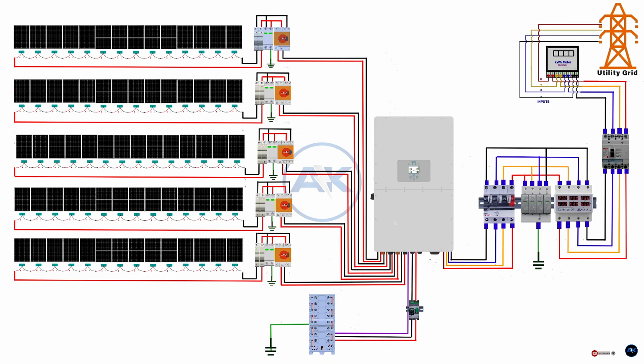Now we install the AC MCB for grid protection. The AC MCB protects the inverter from overcurrent and short circuits. Use a 3-phase MCB rated according to the inverter's AC input current, typically 63 amps for a 40 kilowatt 3-phase inverter. Connect the output of the surge protection device to the input of the AC MCB. From the output of the MCB, run L1, L2, L3, and neutral to the inverter's grid input terminals.